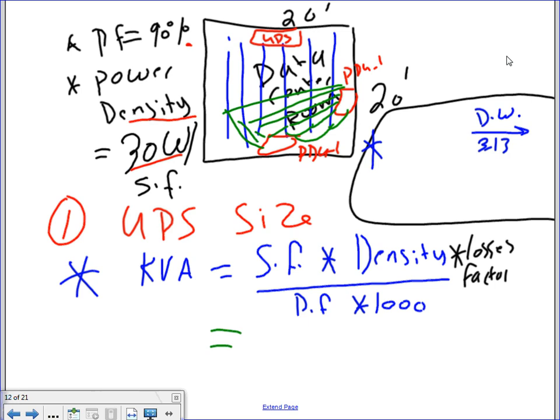Here's the formula I'm going to use. Square footage, SF, multiplied by the density, multiplied by the losses. You can accommodate for the losses with a losses factor, divided by the power factor, divided by 1,000. That will give you the kVA for the UPS. Let's go ahead and plug in these numbers and see what we come up with.